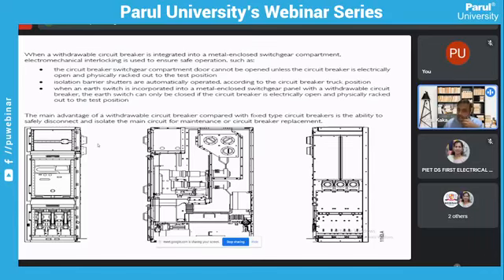Now all these compartments, from a design point of view as well as the type tested switchgear point of view, are separated by metallic partitions. So the point here is that whenever you are doing any maintenance activity on one of the compartments, you can do the maintenance activity without affecting the others.